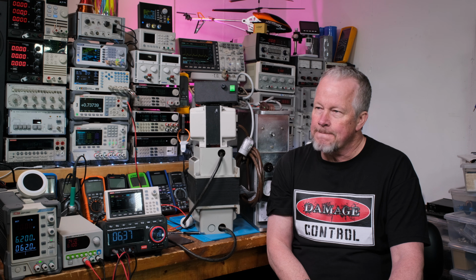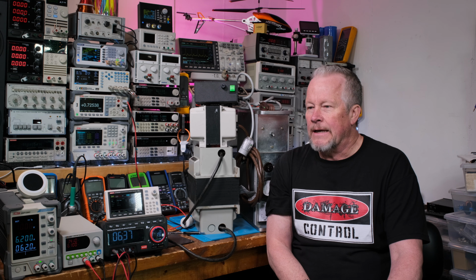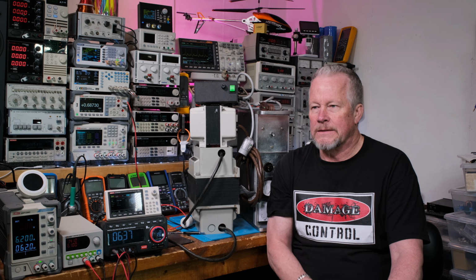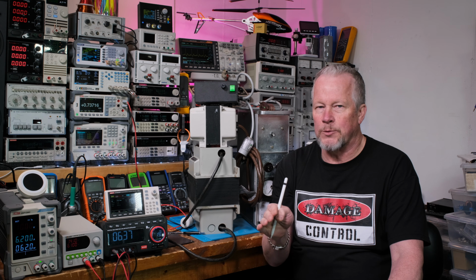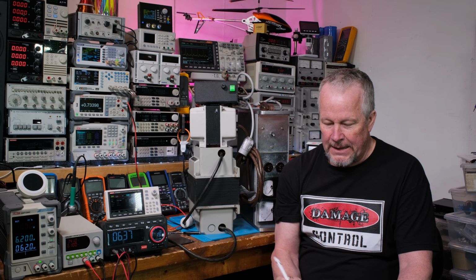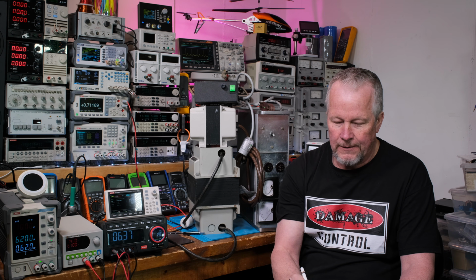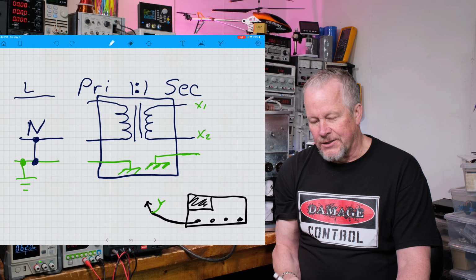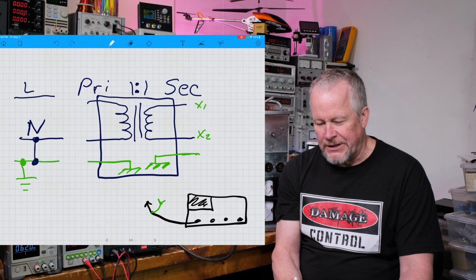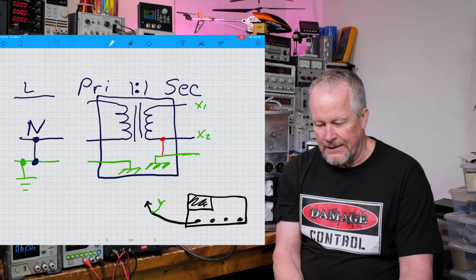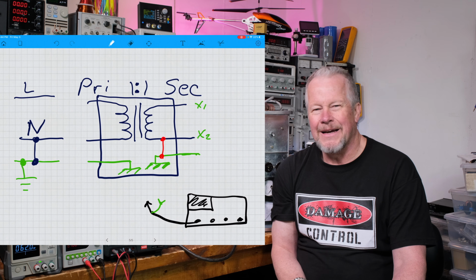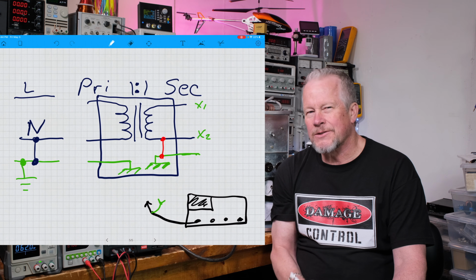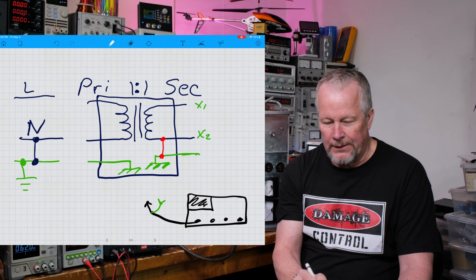So if you're testing, if you've got a test bench and you want a floating output because you know that's what you want, make sure that bond is not there. Alright guys, so on an isolation transformer, usually you just don't want that bond in here. But you might want it, so you have to decide for yourself if you do want that.